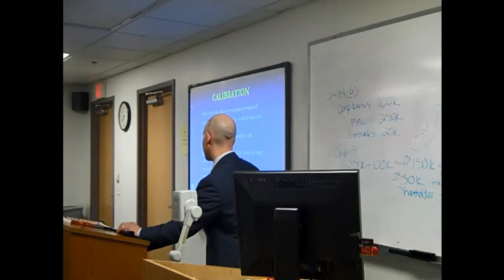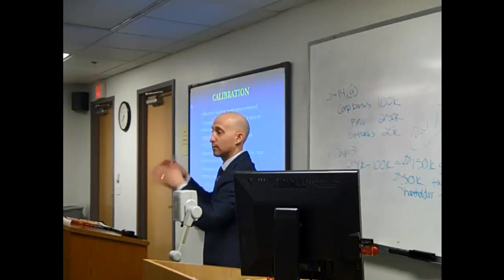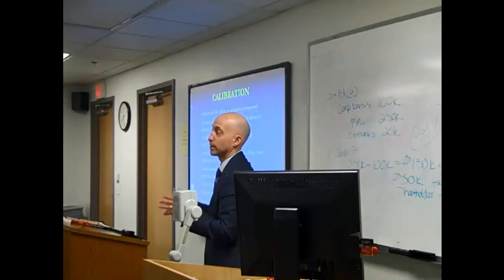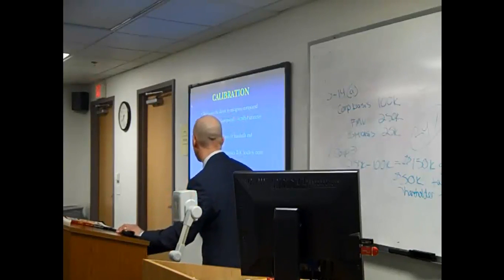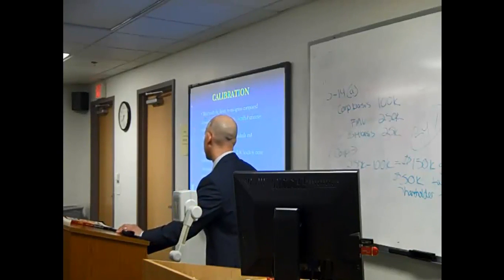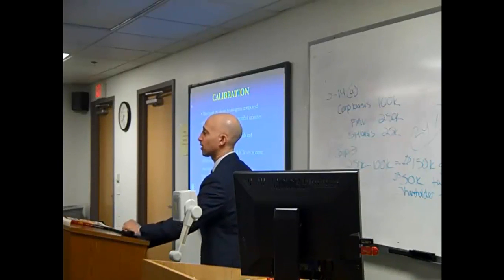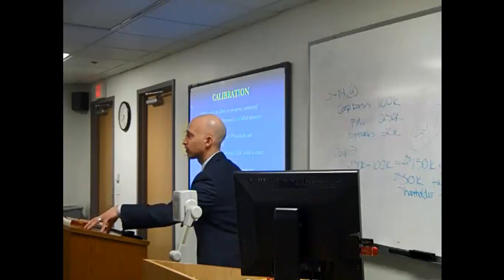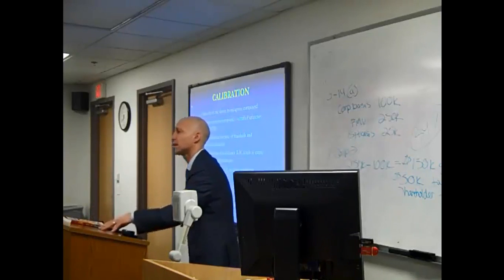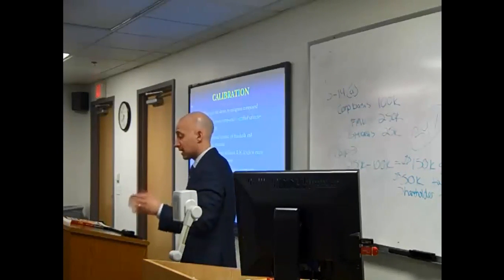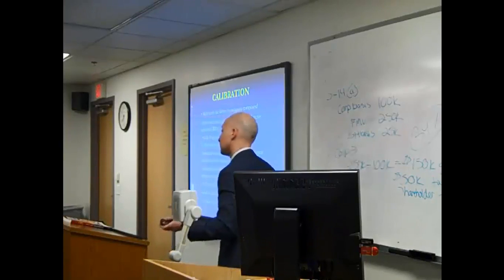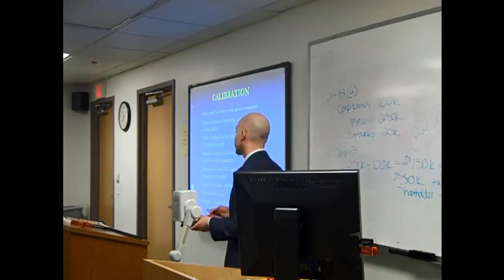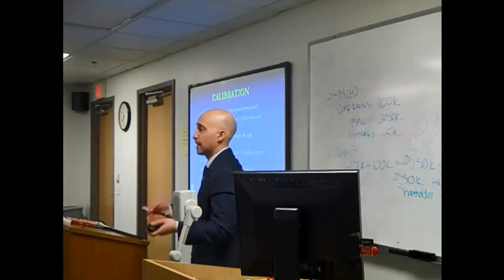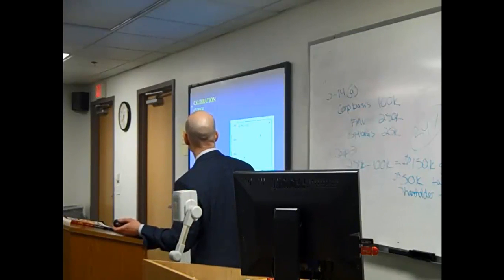The best way of doing it is dual column testing, so you actually have two of these columns set up in the machine as opposed to one. That is the best way to do it. Most labs do not do it that way. Simply put, garbage in equals garbage out. So if the lab can't prove that they did this properly, if they didn't set up the calibration properly, if they didn't do the controls, if they didn't do the verifiers, it's not a good test. And they can't say to a degree of scientific reliability that this is actually alcohol.